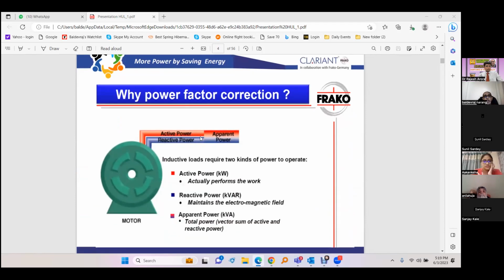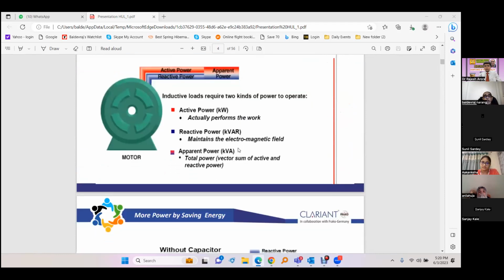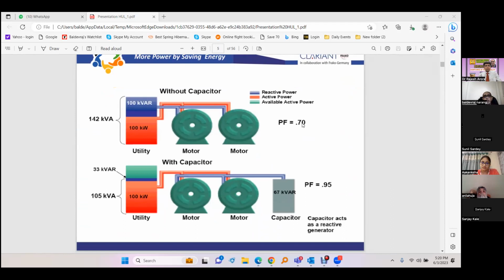So this is another picture. Active power and reactive power are the two items required for running any inductive equipment like a motor, and the vector sum of these is apparent power. I'll just take an example. Suppose we have an inductive load where the power factor is 0.7, and the load is 100 kilowatt, so we are importing 100 kilowatt of active power. Because the multiplying factor here is unity only, reactive power also is 100 kVAr. So we are importing 100 kVAr of reactive power and 100 kilowatt of active power from the grid, and we need a demand sanction of 142 kVA to manage this type of arrangement.